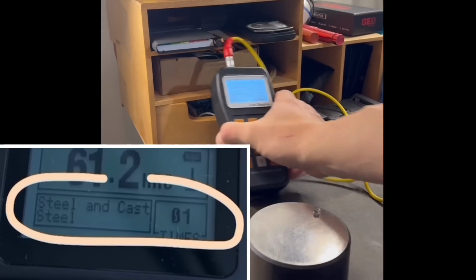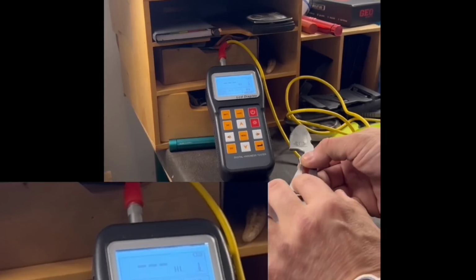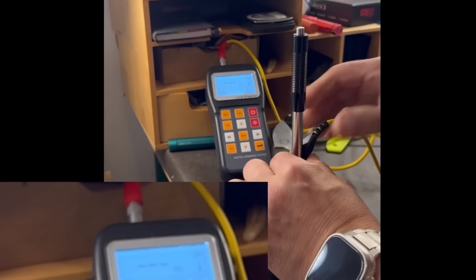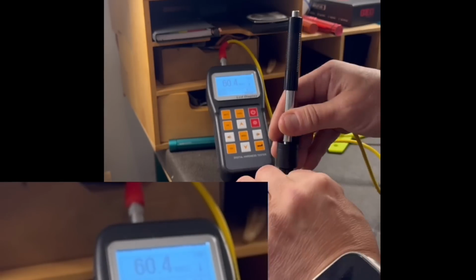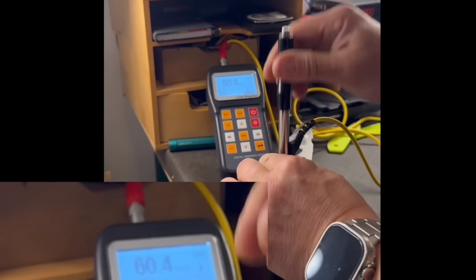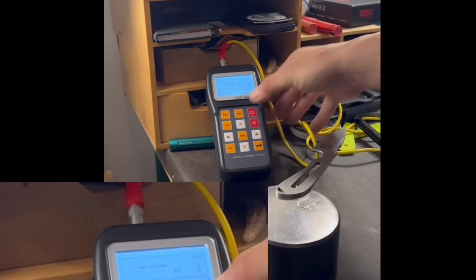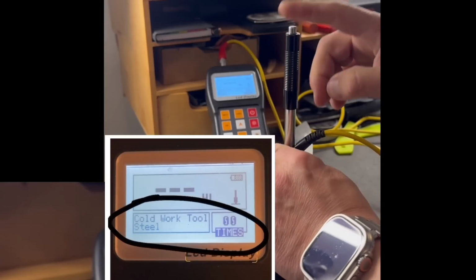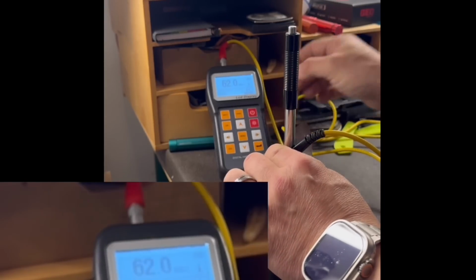First, the Leeb tester will be set to steel and cast steel setting, like it was in the video that I quoted earlier, which is not the setting I used to test all the knives you've seen before, because that is the setting reserved for predominantly steels in the Rockwell B scale. As you can see, at this setting, it is measuring 4 points below benchtop. For high hardness steel, it has to be set to cold rolled tool steel. And that is exactly what I just did there.